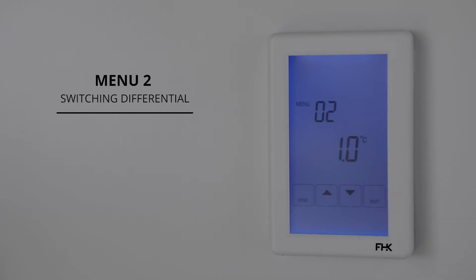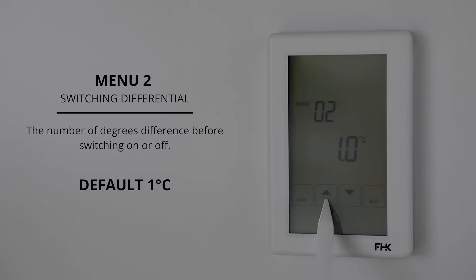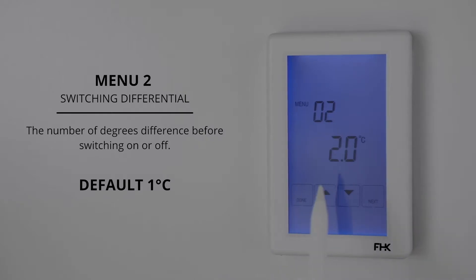Menu 2 is the unit switching differential. Switching differential is the number of degrees difference before switching on or off. So if it is on one degree, your floor will switch on a half degree before your set temperature and switch off a half degree after your set temperature. If you set this at two degrees, your floor will come on one degree before your set temperature and one degree after. Once you have selected your preference, press next.